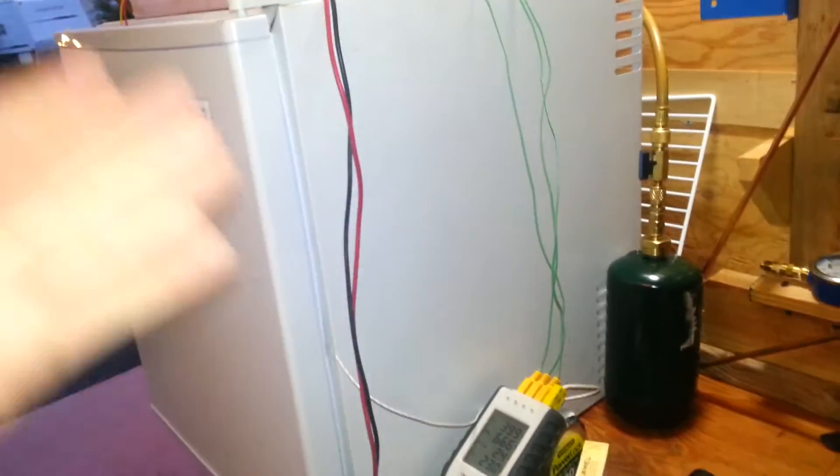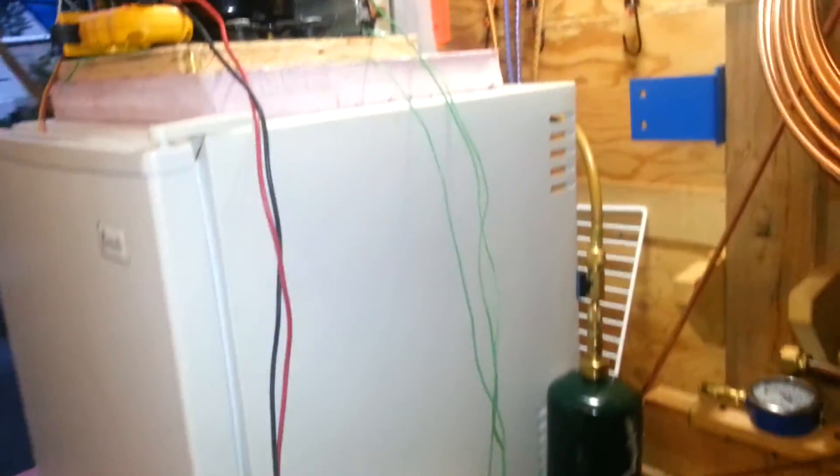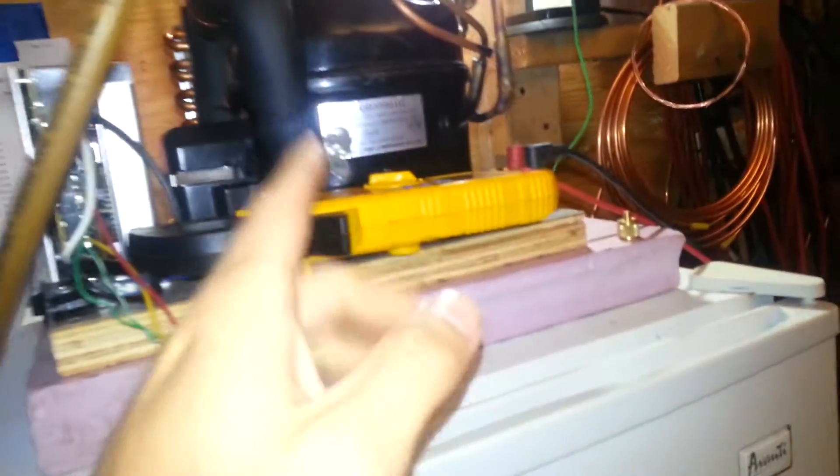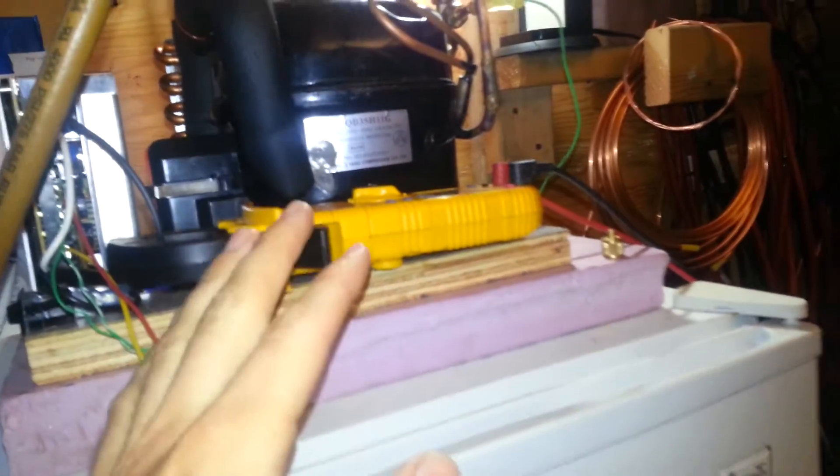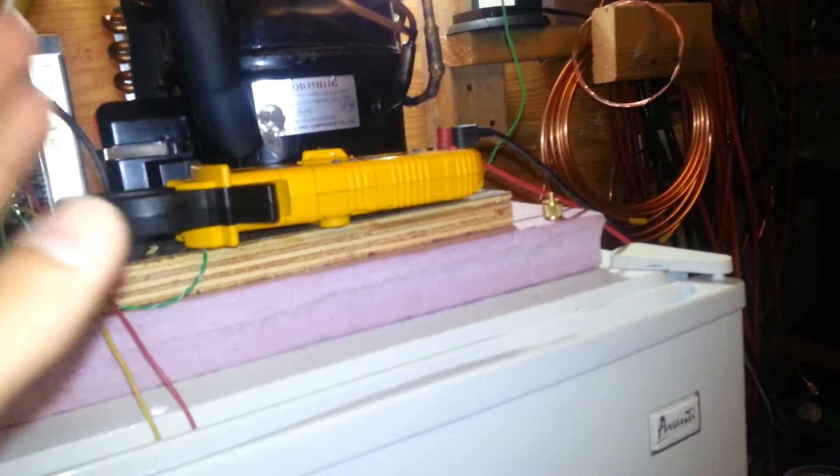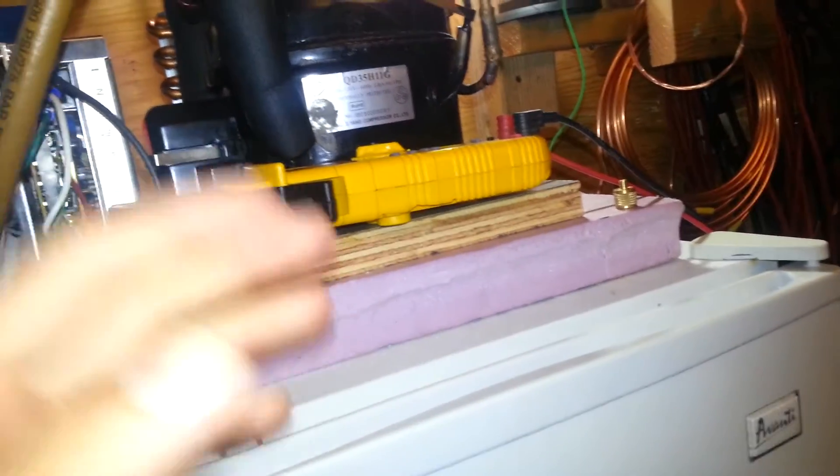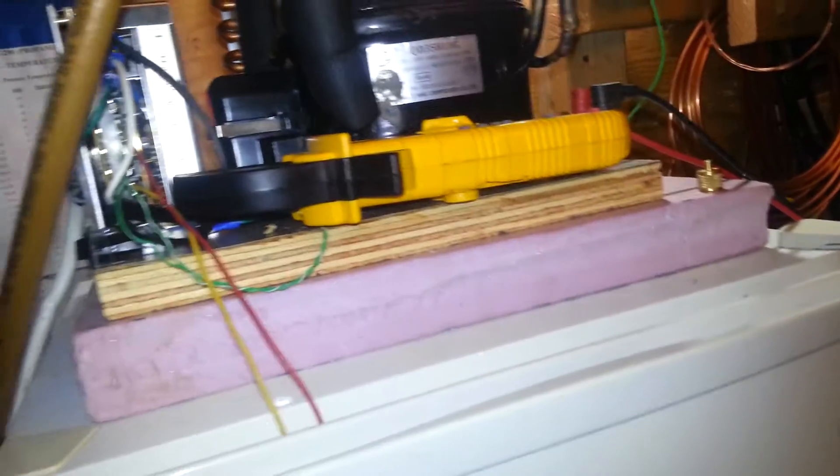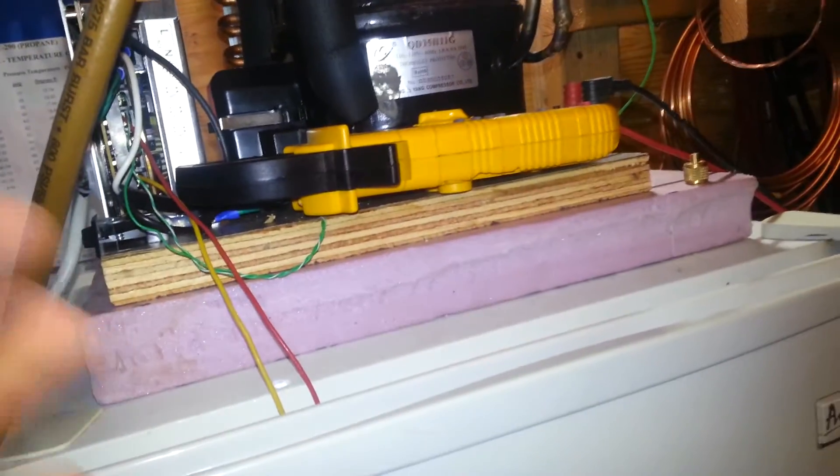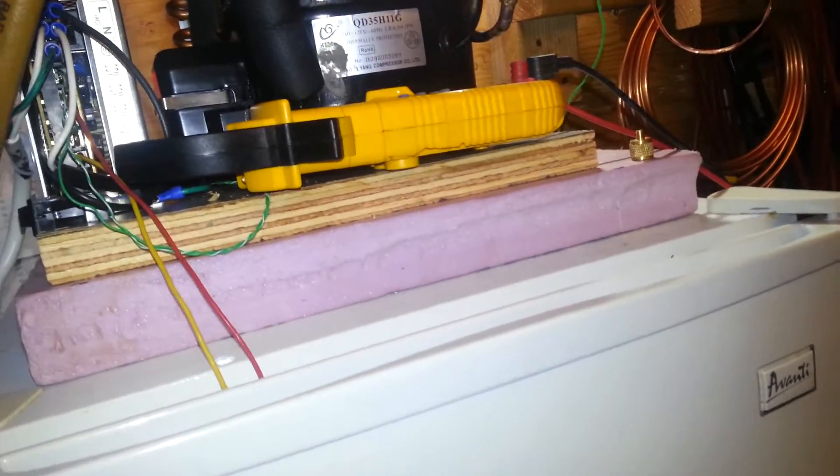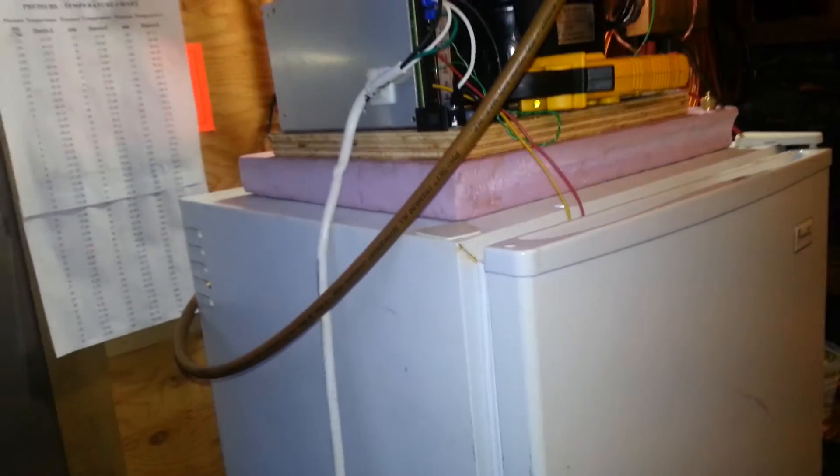But that coil is going to still freeze up pretty bad. Again, the large compressor, if I go to a smaller compressor, it will cool that bucket more slowly but it will probably run more consistently and for longer periods of run time. And I would expect to get a little better performance out of it. So that's exactly what I'm going to do with that small compressor down there.